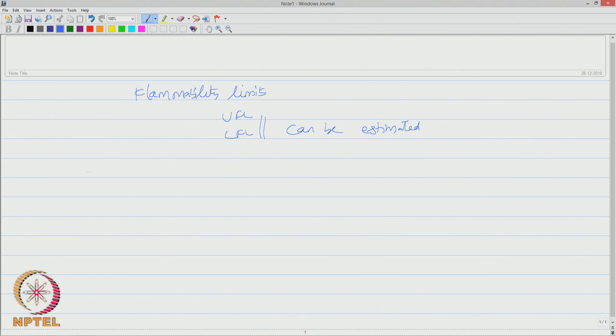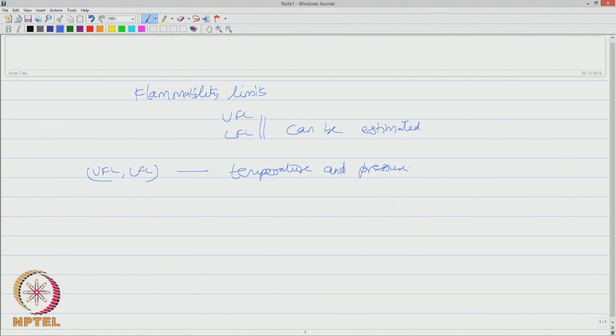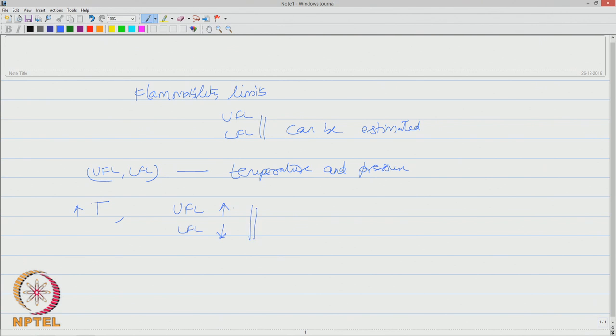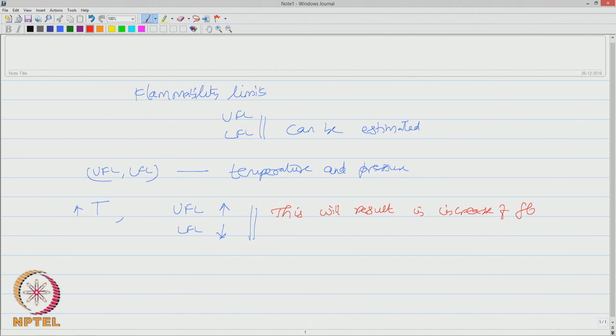Now, these flammable limits UFL and LFL are also dependent on temperature and pressure. When temperature increases, upper flammable limit increases and lower flammable limit decreases, and this will result in increase of flammable region.